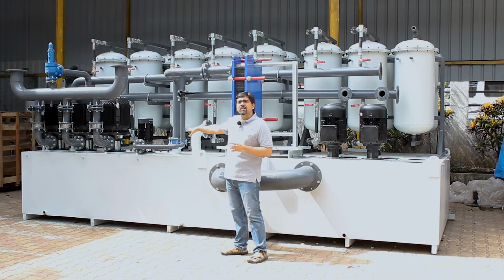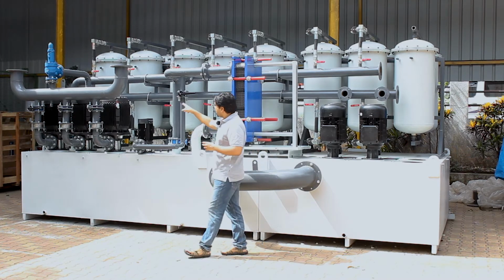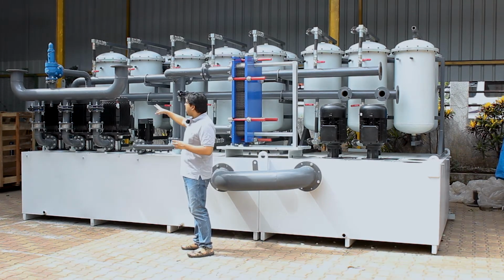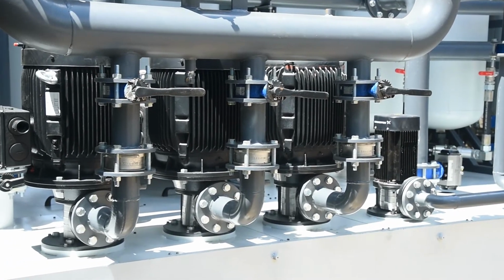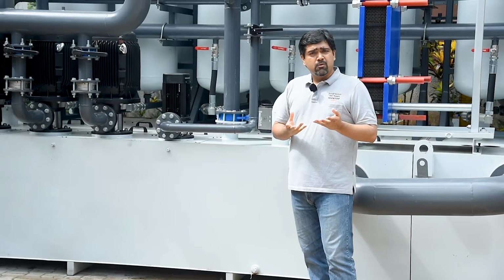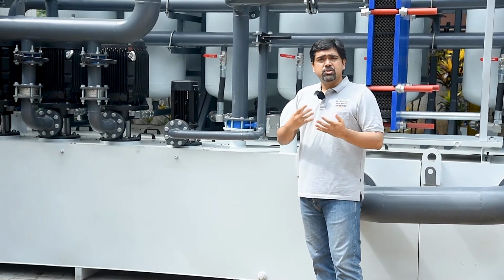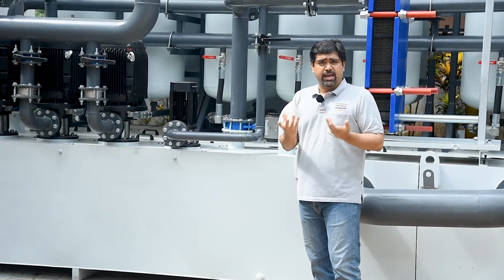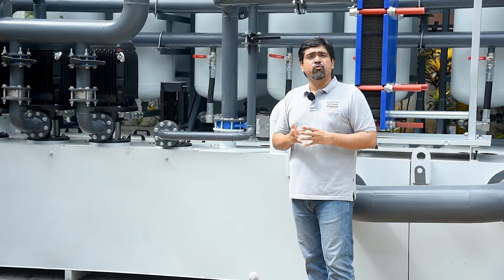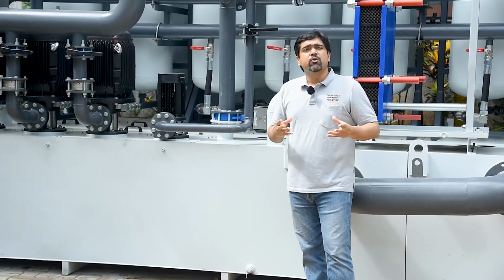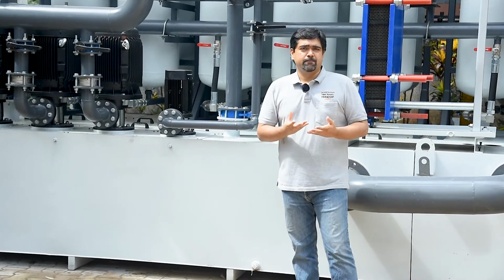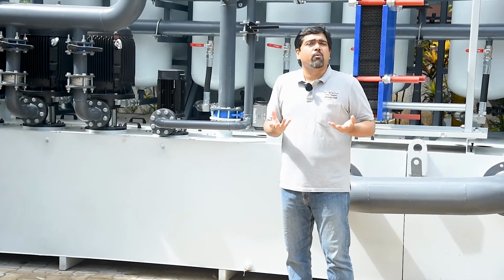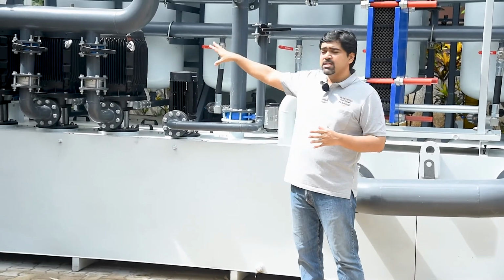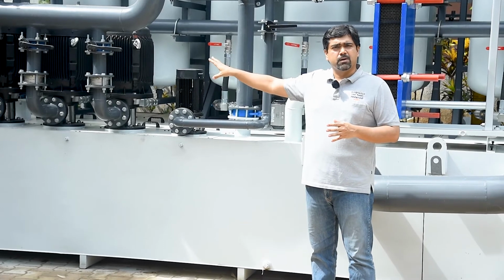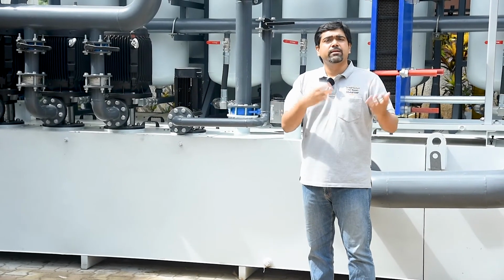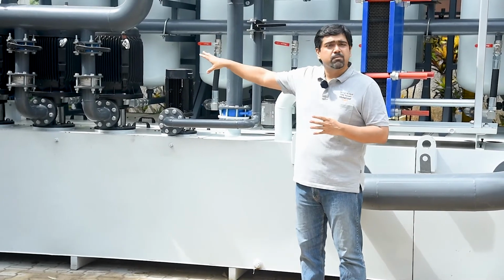Once the level inside the clean oil compartment increases, the clean oil pumps will start. We have provided 3 clean oil pumps. Not necessarily all 3 pumps will start at the same time. It is a sort of automation again. Since this unit is going to be connected to 14 grinding machines, there can be a scenario when certain machines are not in operation. At that time, the total flow is not required to be supplied. So in that case, one or two of the pumps will stop, and as and when the requirement increases, the pumps will start again.